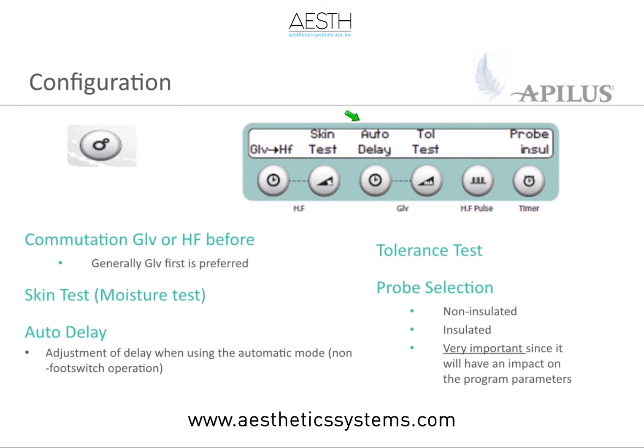The auto delay deals with auto mode. So when we work auto mode, we work without the foot pedal. When we work without the foot pedal, we need to set a delay into how long do we give ourselves to do an insertion before the machine delivers the current. This is where I would come in and put that type of delay. Tolerance tests, you would see this when you are in the blended galvanic modes. This is to test the client's tolerance to galvanic current or milliamps so that you can then use that to go back and manually adjust a blend setting.